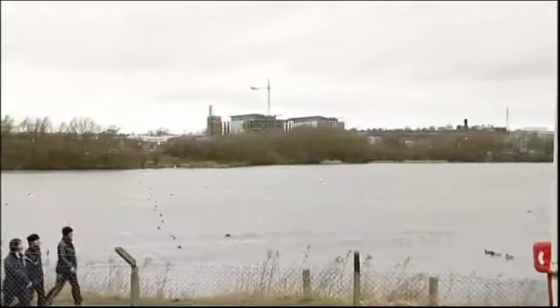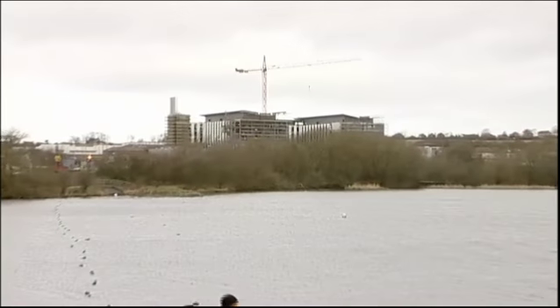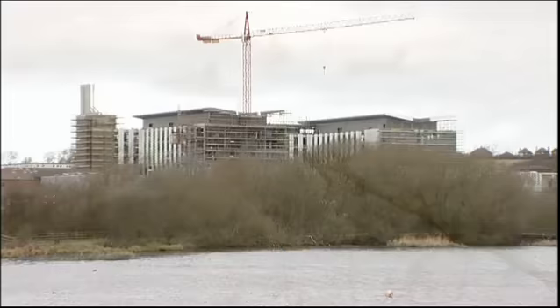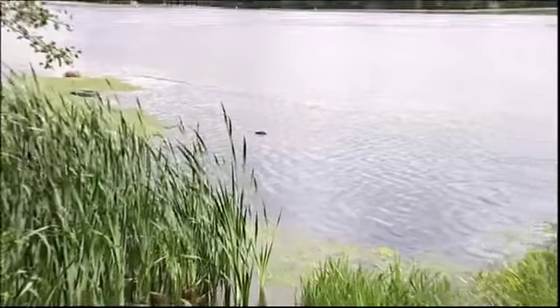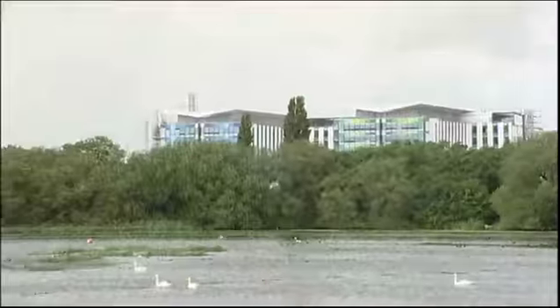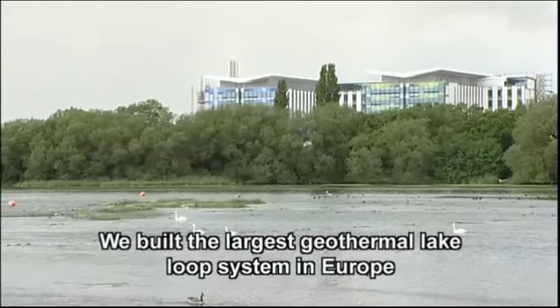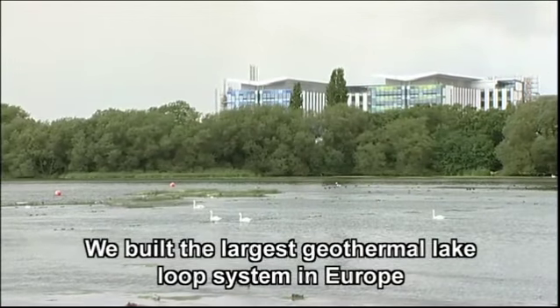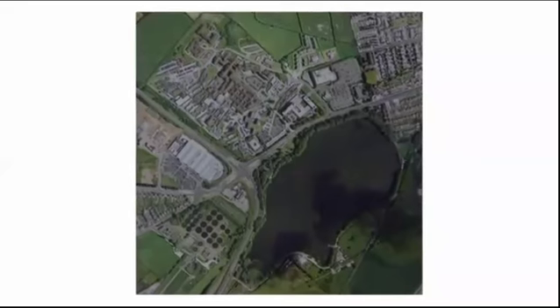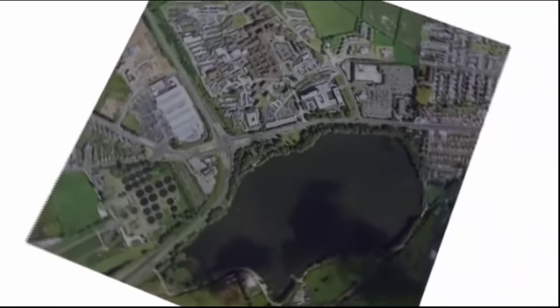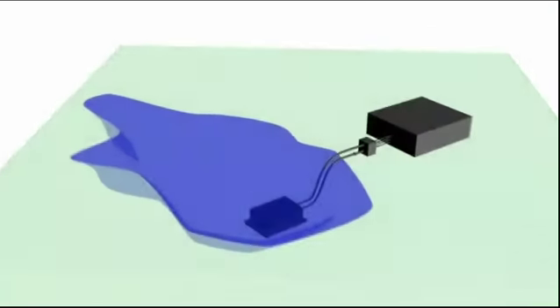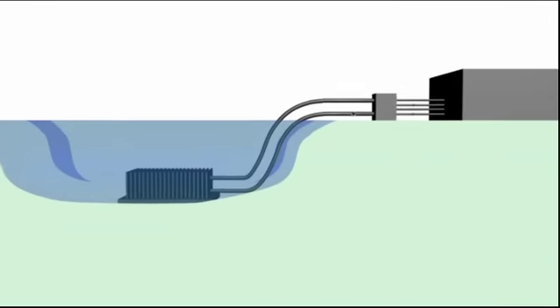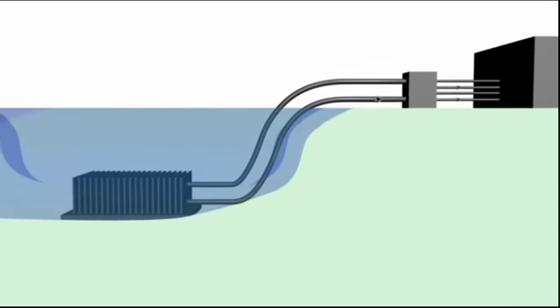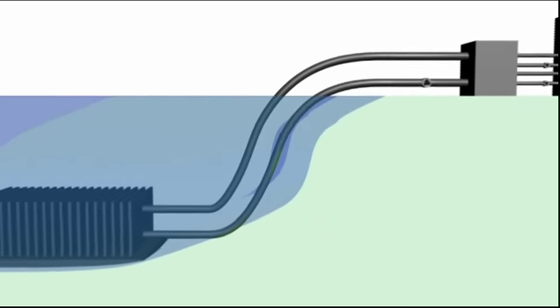After surveying the local geology, we decided a closed-loop system using the nearby 65,000 square metre Kingsmill reservoir would provide the optimum balance of maximum energy generation with minimum environmental impact. In fact, what we built is the largest geothermal lake loop system in Europe. The Kingsmill scheme consists of a network of stainless steel plates called slim jims that are secured within frames and submerged in the reservoir. They're connected by underground polyethylene pipes to the hospital's plant area.